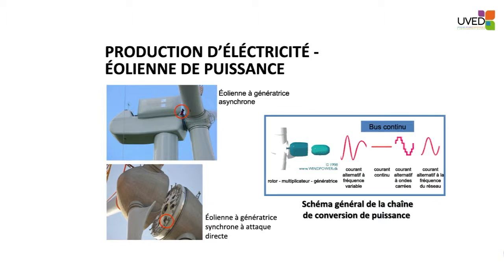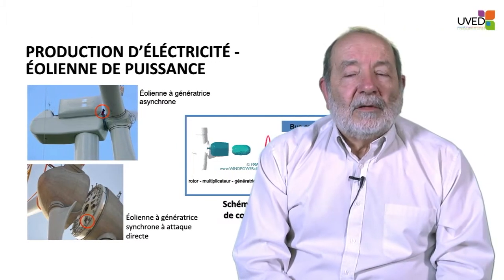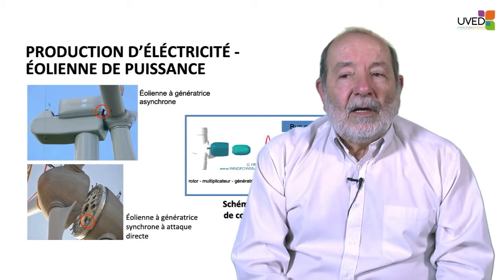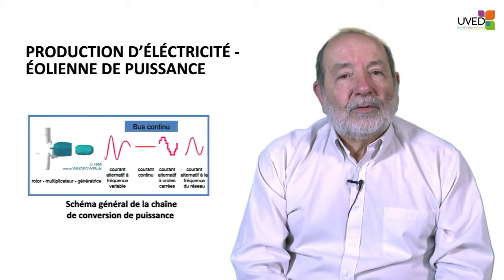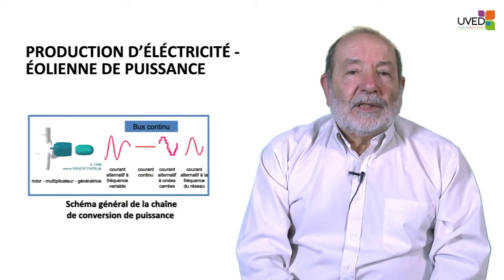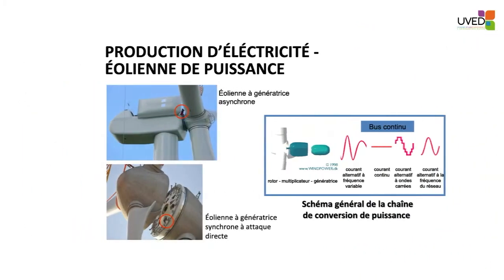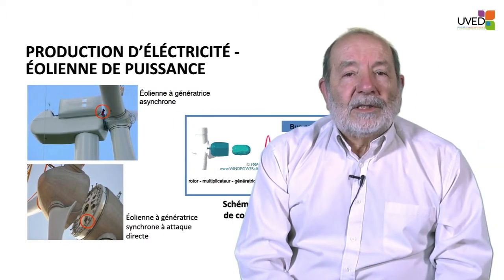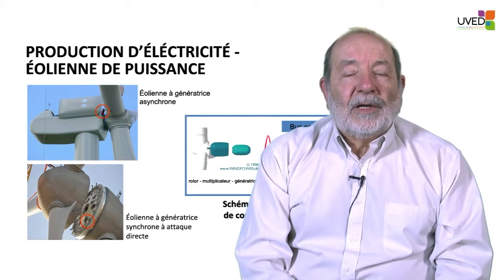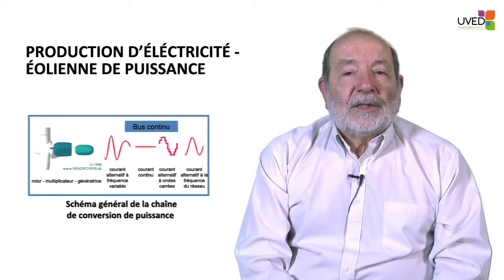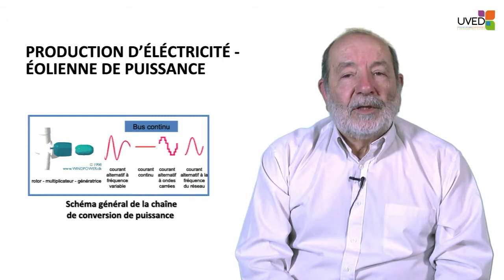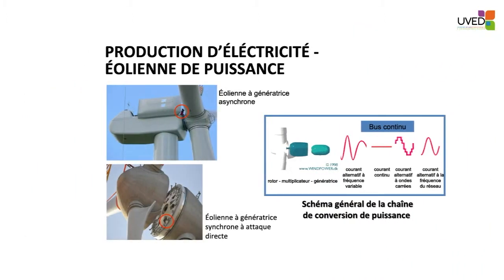Regardless of the type of generator, the current produced is an alternating three-phase variable-frequency current. When the windmill starts, the frequency changes depending on the rotor's rotating speed. It is impossible to connect directly to the grid where frequency is fixed. It is therefore necessary to go through a DC bus, so the current is rectified using rectifiers to supply a continuous voltage, from which an alternating current with fixed frequency is produced using inverters.